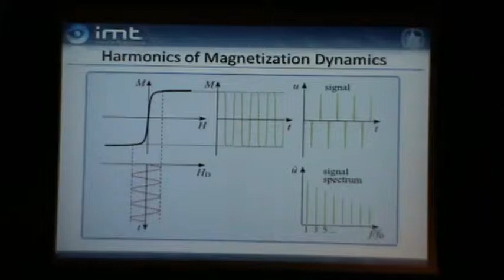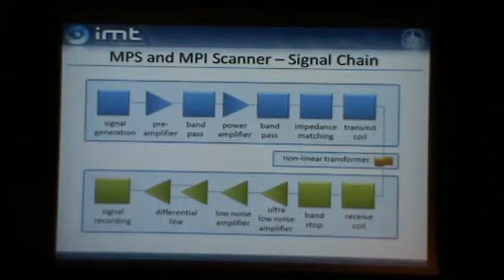This is something we started with by designing the signal chain, and you see here in blue the transmit chain, and in green the receive chain. And here, of course, you need signal generation, a lot of amplification, band passes, where you produce a very harmonic sinusoidal excitation, because you would not like to have harmonic waves already in your transmit path that cover the reaction of the nanoparticles. So then you have the nanoparticles, and measure in the receive coil the small signal from the particles, leading this to a bandstop filter, filtering out the fundamental frequency, and doing ultra low noise amplification before you record the signal.